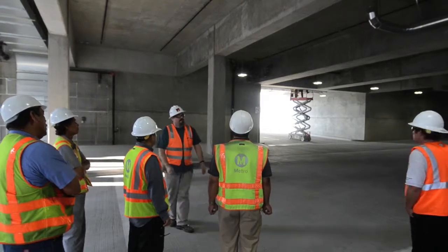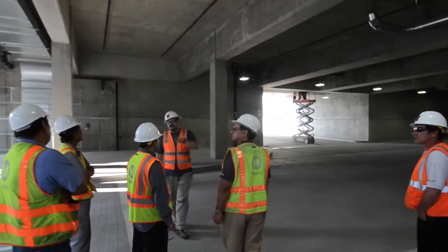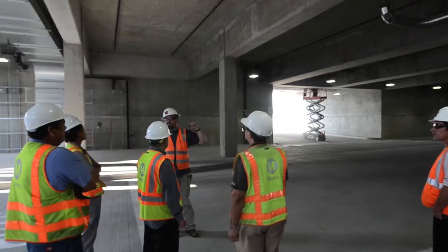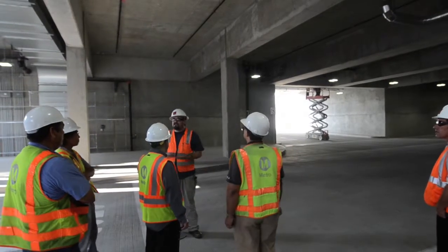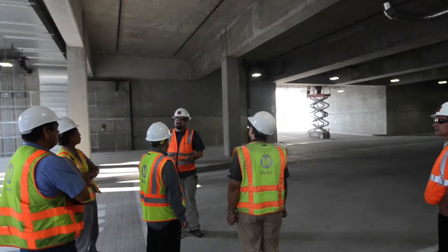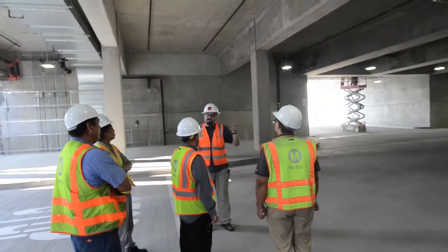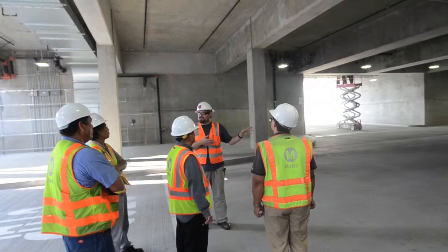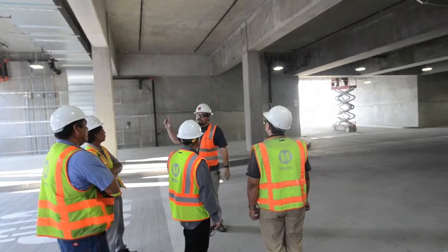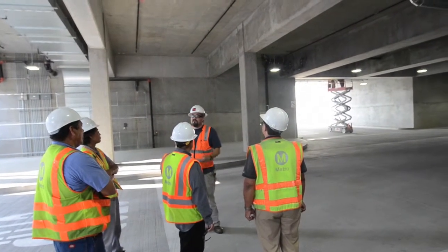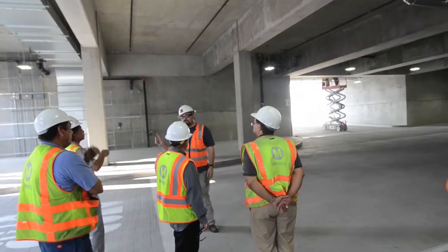Is there anything we do after that goes off? No, because like you said, it will self-correct unless it goes into trouble, like there's an issue with the board or it goes bad. That's a different story. But if it's just an alarm because it sees too much methane, it will go off. But when the fans blow, they'll blow it out, and then it should go back to regular. But you do have to go back up there and hit reset on the panel. That's the only thing you would have to do, go to the panel.